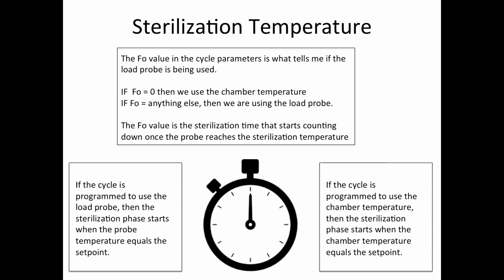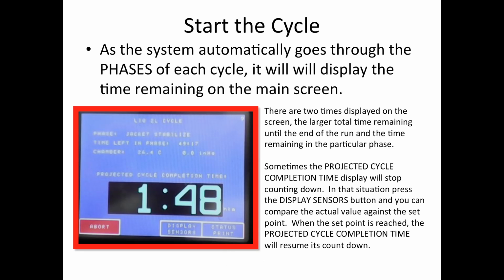On the second page of the cycle parameters menu, you'll see something called the F0 value. If F0 equals 0, then we're simply using the chamber temperature to know when to start the sterilization. However, if F0 equals anything else, then we are using the load probe. The F0 value is the number of minutes for the sterilization time, and it will start counting down when the probe reaches the preset sterilization temperature. Now we are ready to start the cycle.